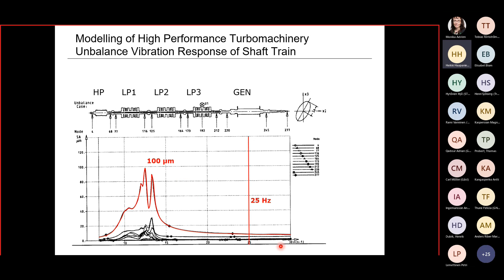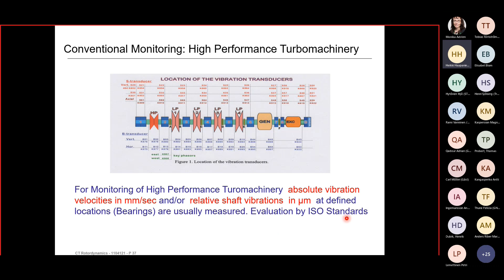Now let's come to the next part, the monitoring part of high-performance turbo machinery. And I will subdivide this again into conventional monitoring as we do it today, and an idea how a future model-based monitoring and diagnosis could look like. I start with the conventional monitoring. That's what most of you know, I think. For monitoring in such large machines, absolute vibration velocities in millimeter per second are measured usually at the pedestals, and relative shaft vibrations in micrometer are measured at locations of the bearings. So that means between the stator part, the bearing, and the bearing pedestal and the shaft line. And these values are measured and can now be evaluated by, for example, ISO standards to see whether we are in the allowed range or not.